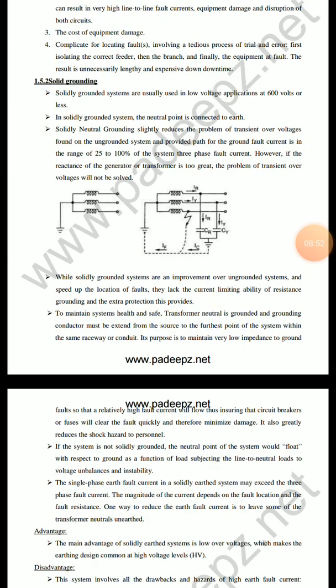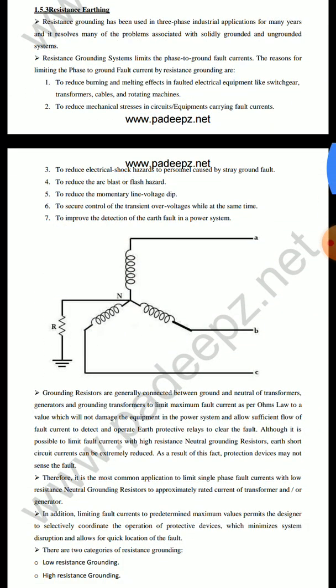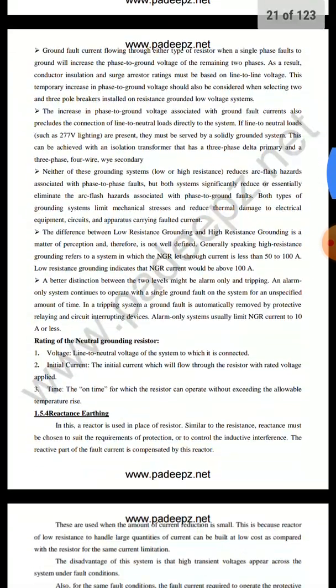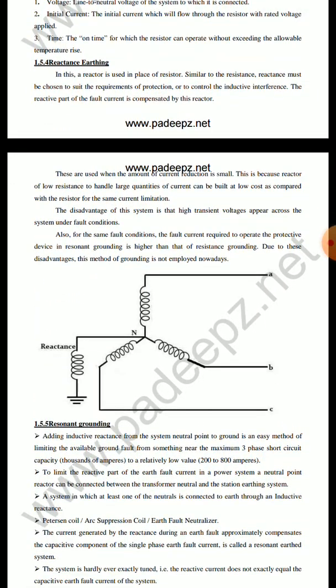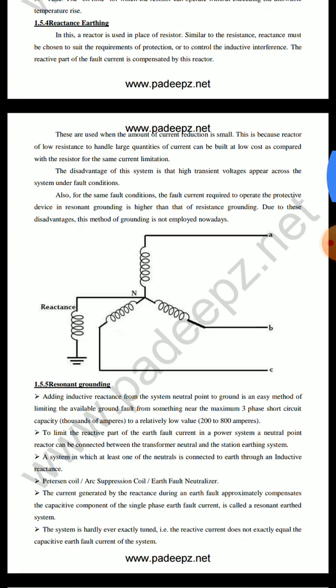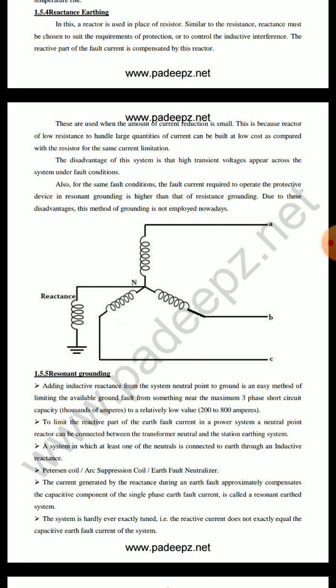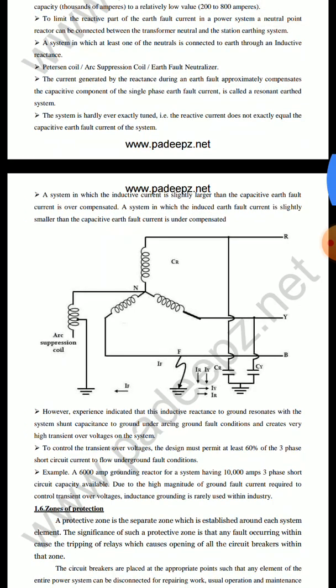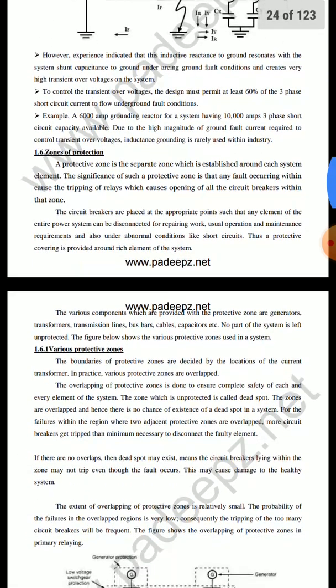Here solid grounding means we connect the neutral directly to the ground, and this is the initial method we generally use. The next one is resistance earthing, where we use a resistor in the grounding connection. We can replace that resistance with a reactance, and this is the major difference between resistance and reactance grounding. Then there is resonant grounding, where we can adjust the reactance level. This is its major difference, and we are already well acquainted with these concepts.